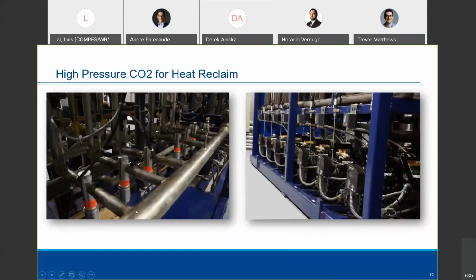And I show this picture because this happens to be an application where we're using CX valves for heat reclaim. So this real OEM has a discharge, CO2 discharge gas header that goes through a valve, and when they needed heat at a part of the supermarket, they would send this right up into the ventilation. There was a heating coil there with direct CO2, and that's another application for the CX valves.